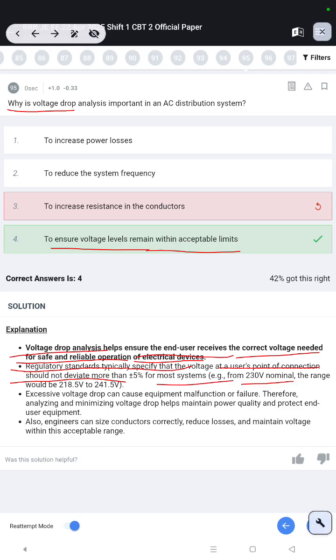The range would be as specified. Excessive voltage drop can cause equipment malfunctions or failure. Therefore, analyzing and minimizing voltage drop helps maintain power quality and protect end user equipment. Also, engineers can size conductors correctly, reduce losses and maintain voltage within this acceptable range.